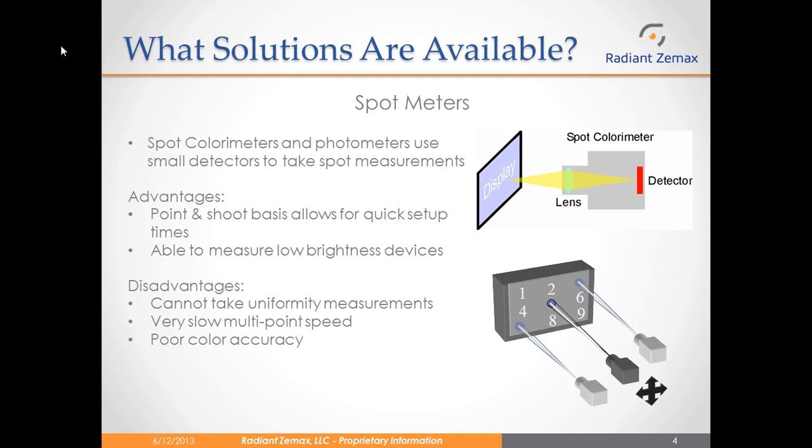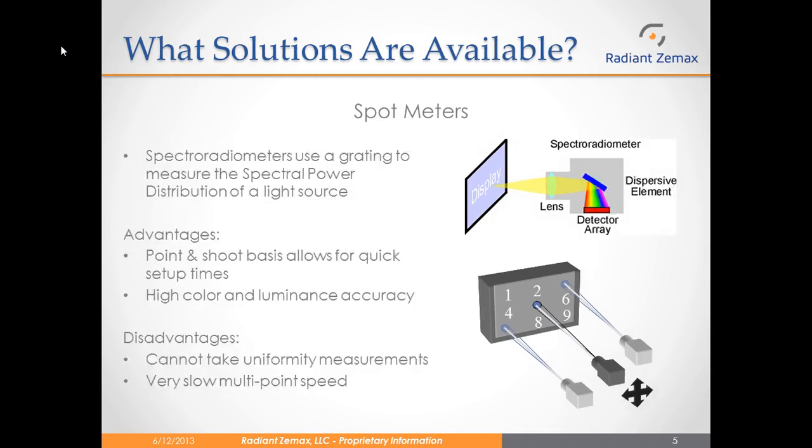In the example on the right, if you wanted to measure nine points on that display, you would have to move the spot meter nine different times. Also, these spot meters had poor color accuracy. Another type of spot meter used are spectroradiometers, which use a grating to measure the actual spectral power distribution of the emitting source. The advantage is that because they are measuring the SPD, you can get high color and luminance accuracy, and they are point-and-shoot, which allows for quick setup times. The disadvantage, again, is that you cannot take uniformity measurements and you have very slow multipoint speed.